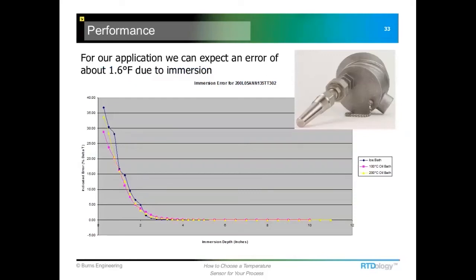And this is a graph that we constructed based off of some testing, and we're getting about 1.6 degrees Fahrenheit just due to that short 2.5-inch immersion that we have in our example process. And if we look down here, we can see that we get down about 4 inches is where most of it goes away. It can maybe even go a little bit shorter on a thermowell like this, but usually about 4 inches will pretty much eliminate the stem conduction in most fluids.